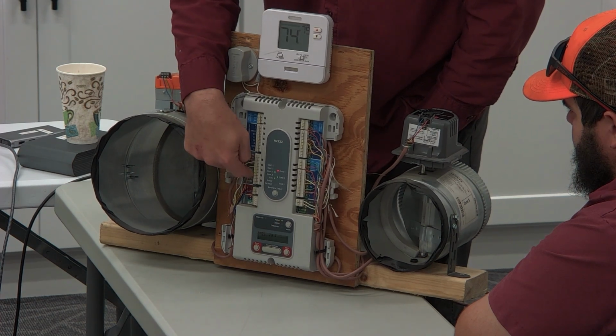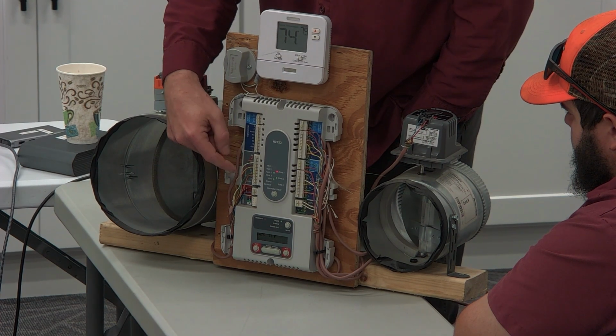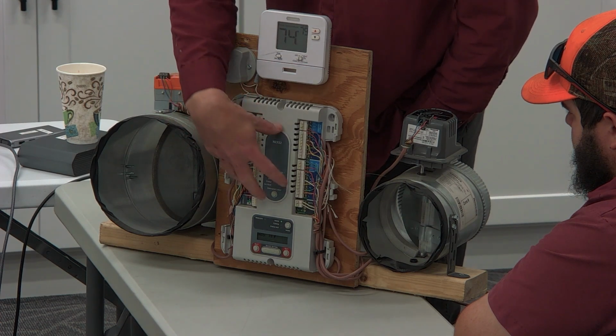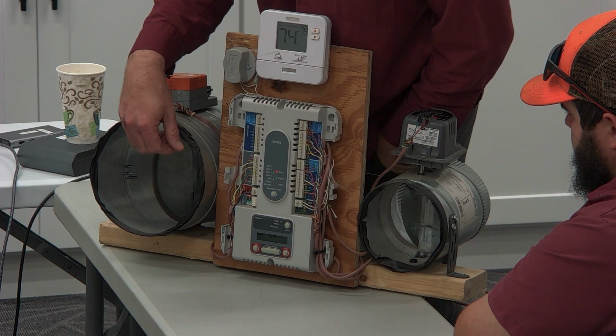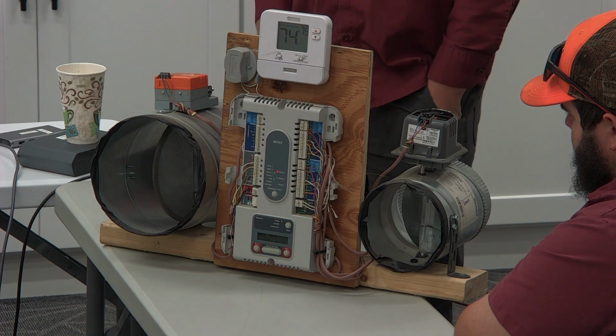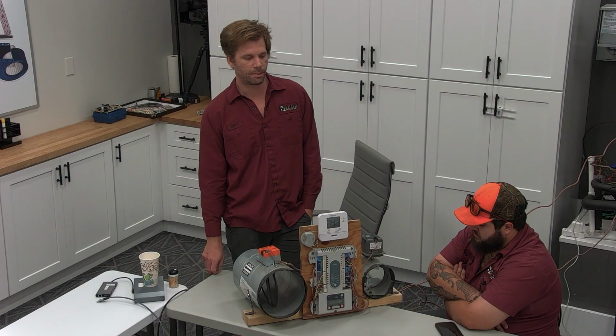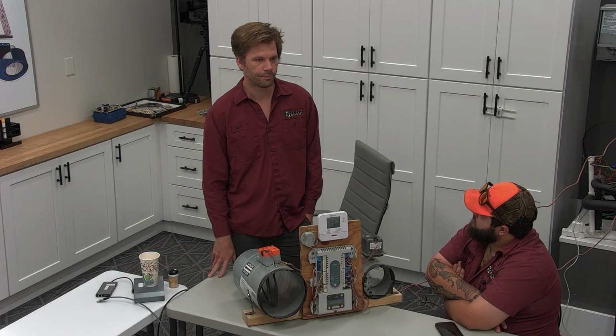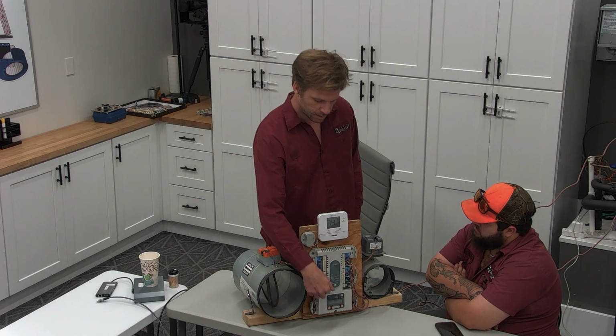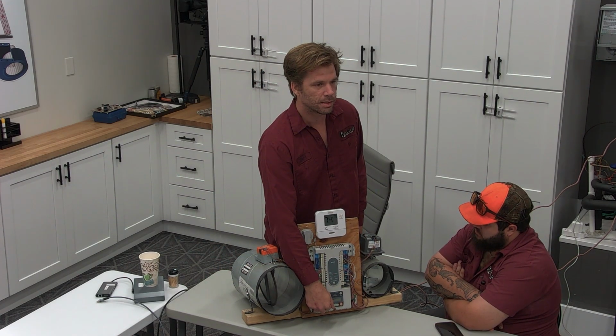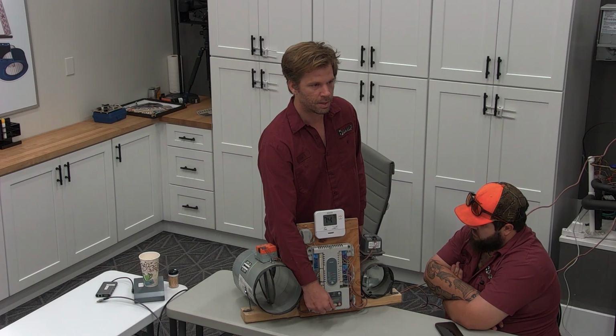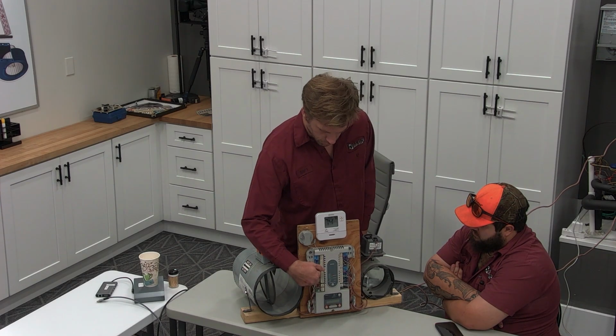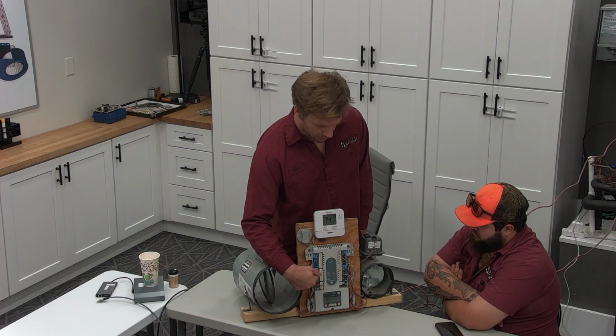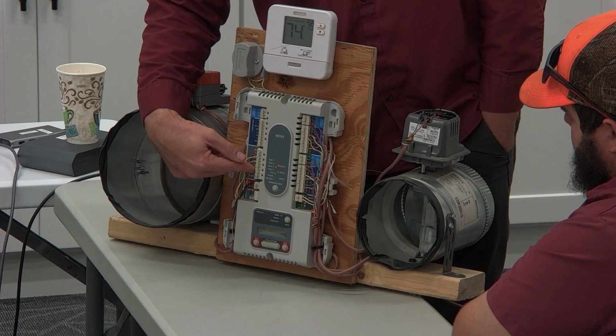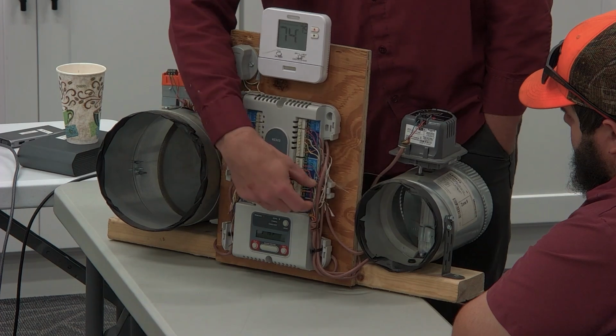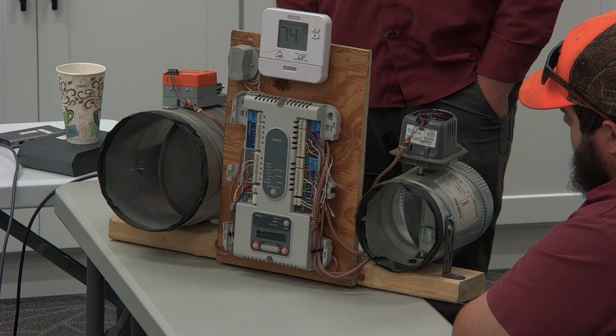So if you have O plugged in, it's a heat pump. If you don't have O plugged in, it's conventional. Whereas this, you have the ability to use this board and wire it up as conventional. You can have a conventional thermostat, but it still controls a heat pump system. And so you can go into the install settings and say thermostat 1 is conventional, thermostat 2, heat pump. And then if thermostat 1 calls for heat, it'll de-energize O, even though thermostat 1's not getting any type of O communication.